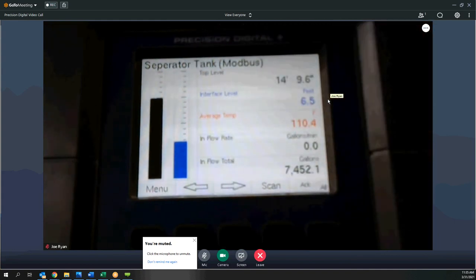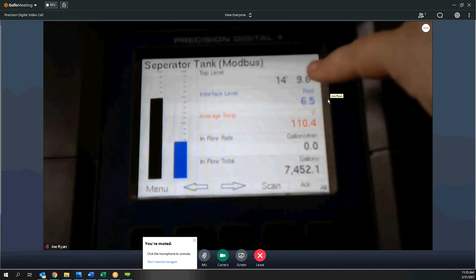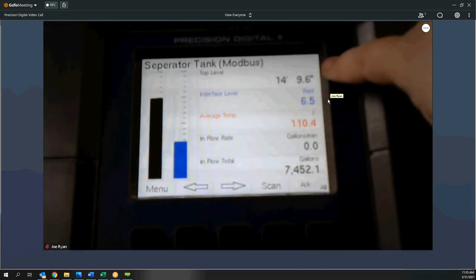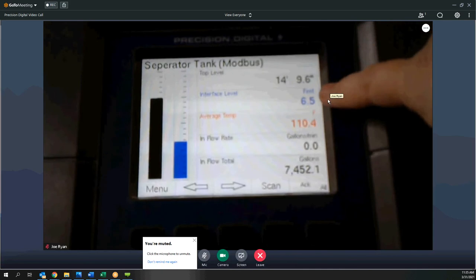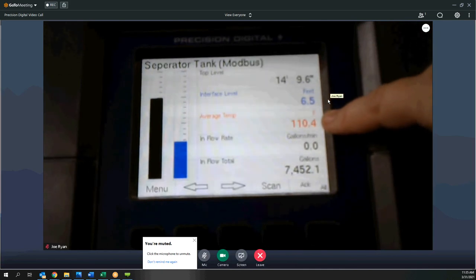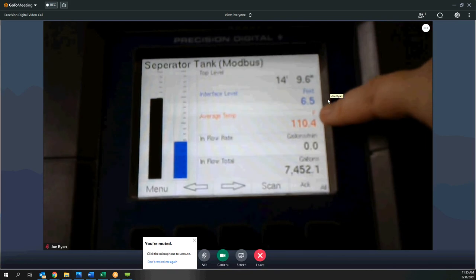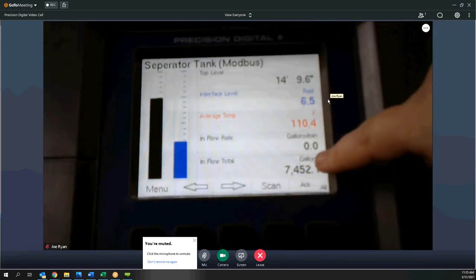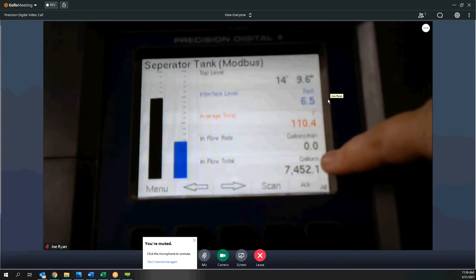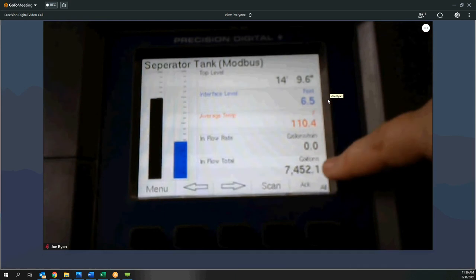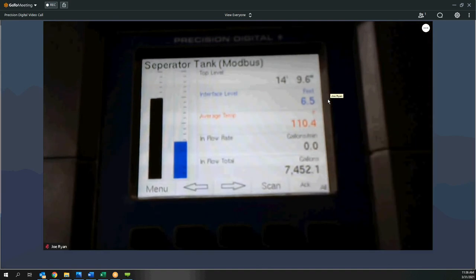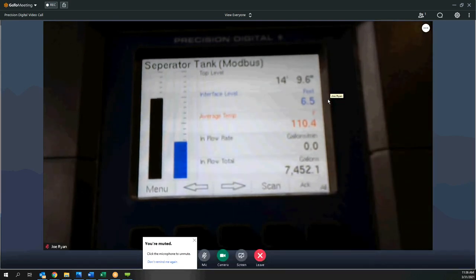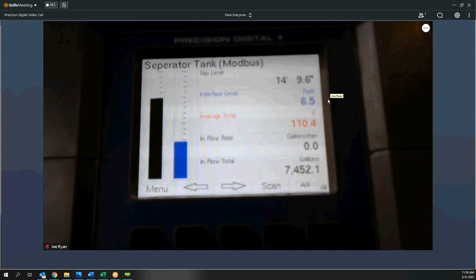Here's the separator tank example — this is the screen I really wanted to show because it's based on all Modbus inputs. I've got top level being pulled out of a transmitter, shown in feet and inches. Then interface level shown in feet, average temperature shown in red, and a connected flow meter for inflow rate and flow total — both of which are just Modbus variables pulled out of the flow meter. This is a great product for people unfamiliar with Modbus because it's so easy to program it to pull out information from Modbus transmitters and flow meters.